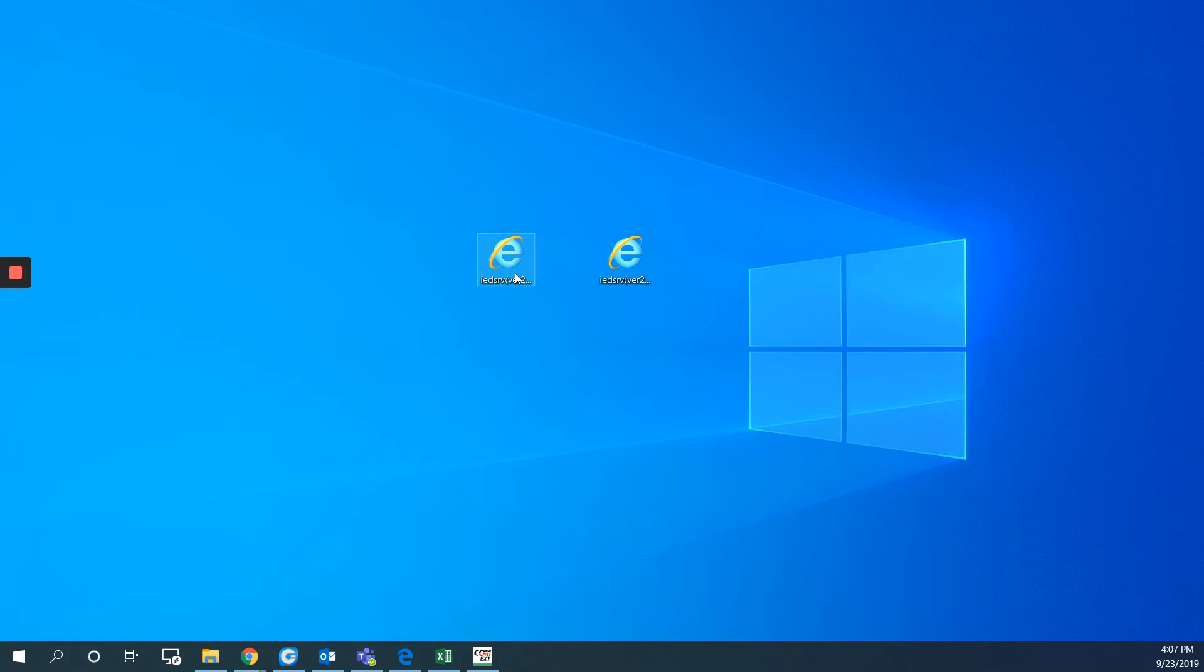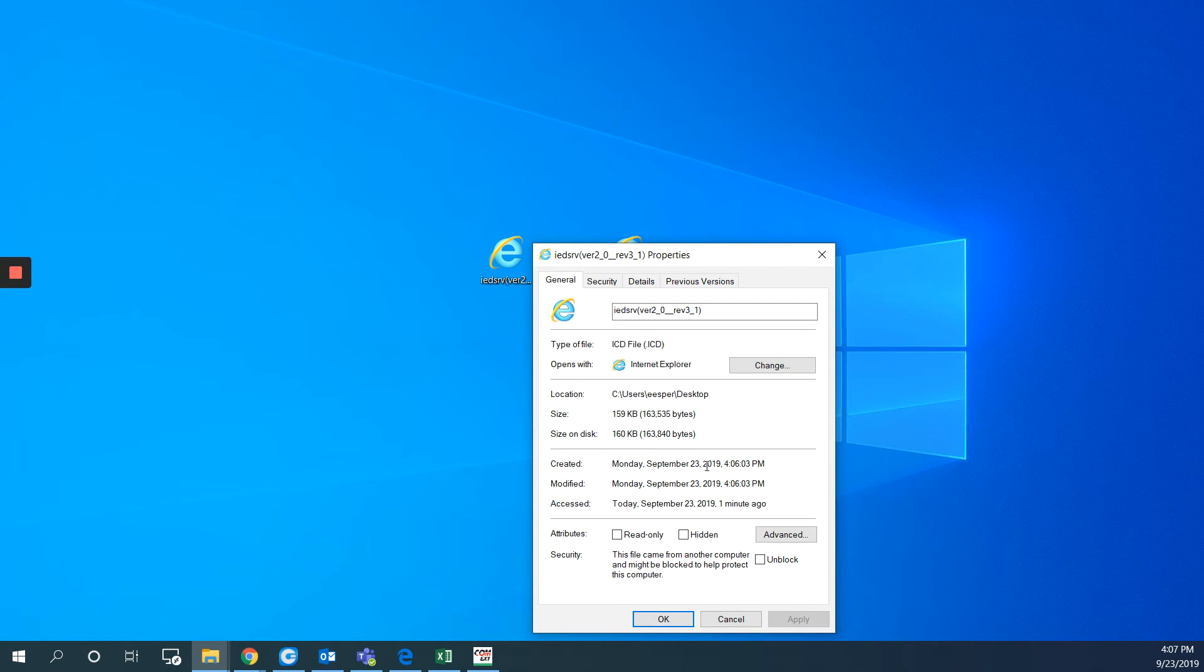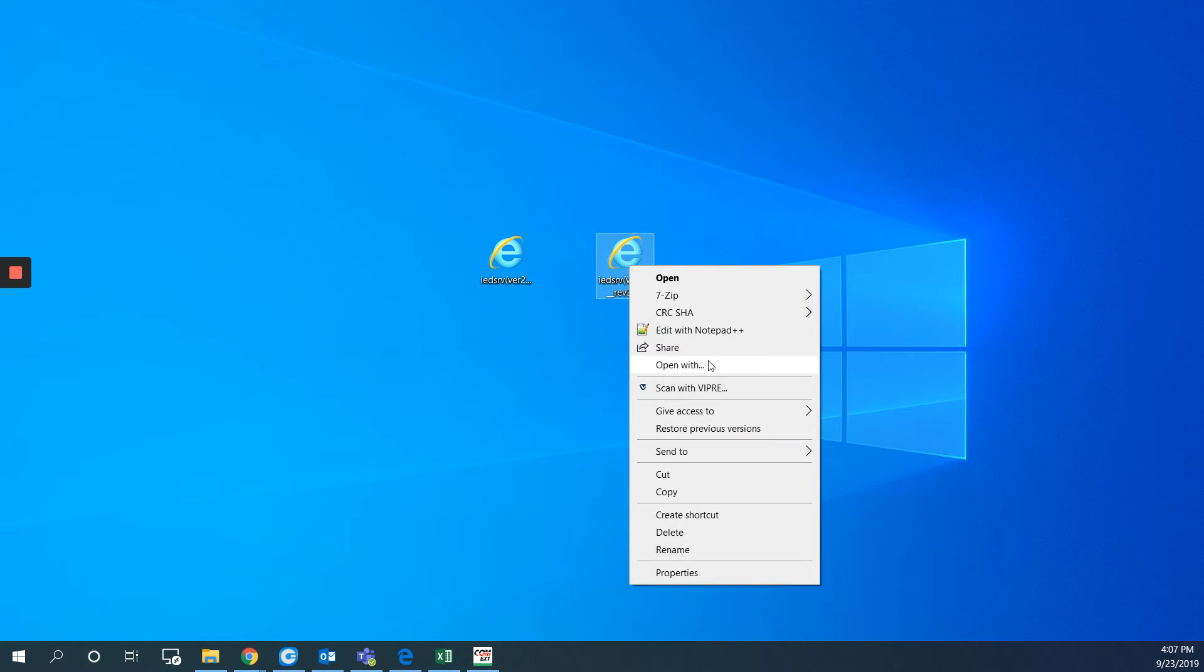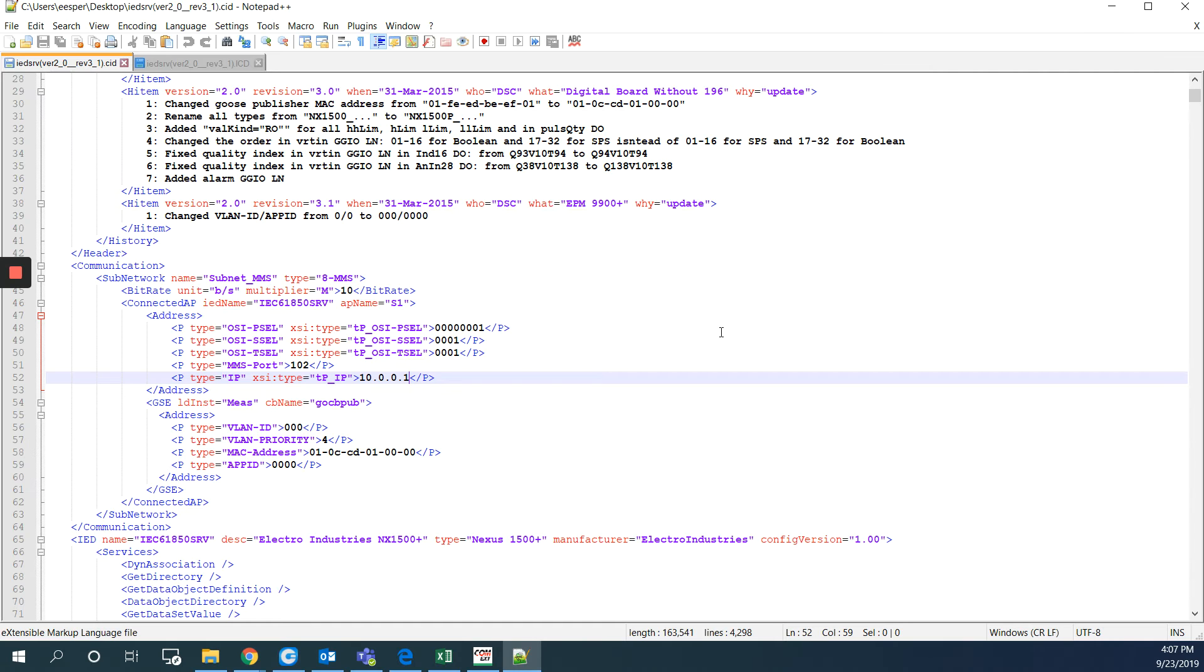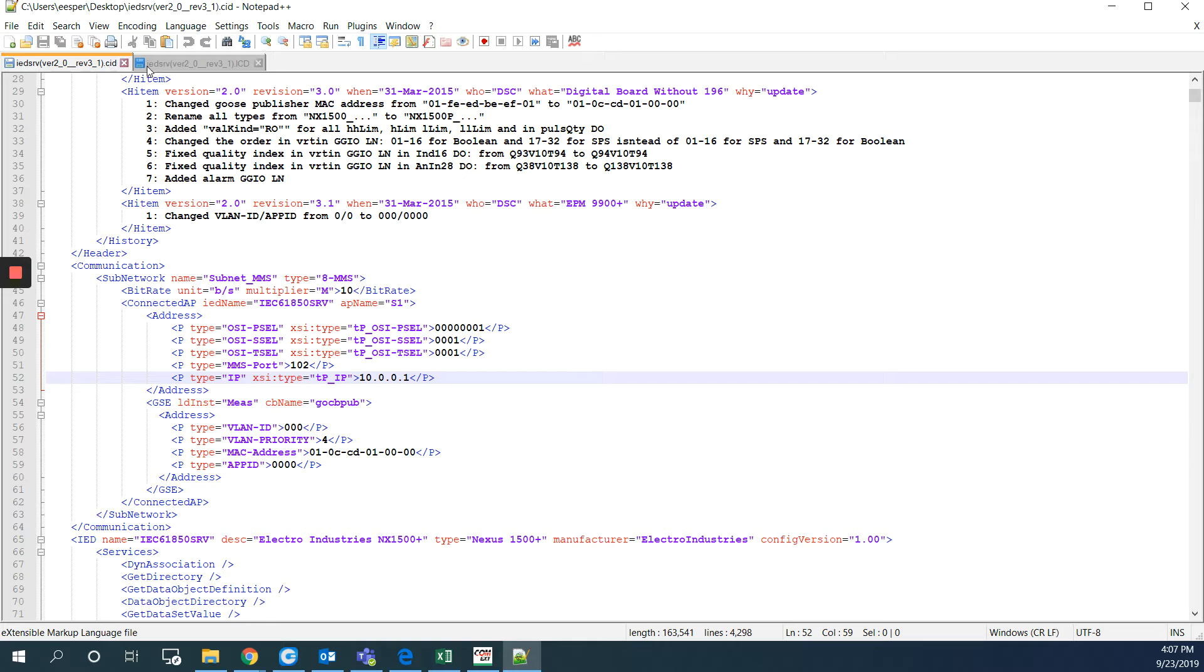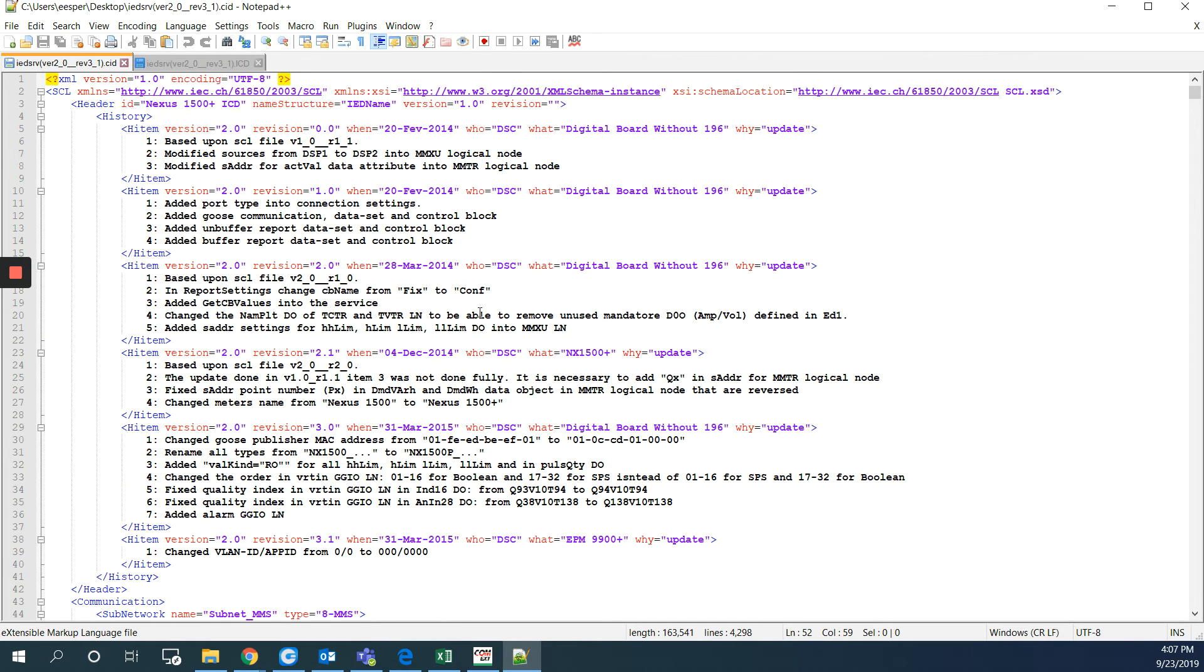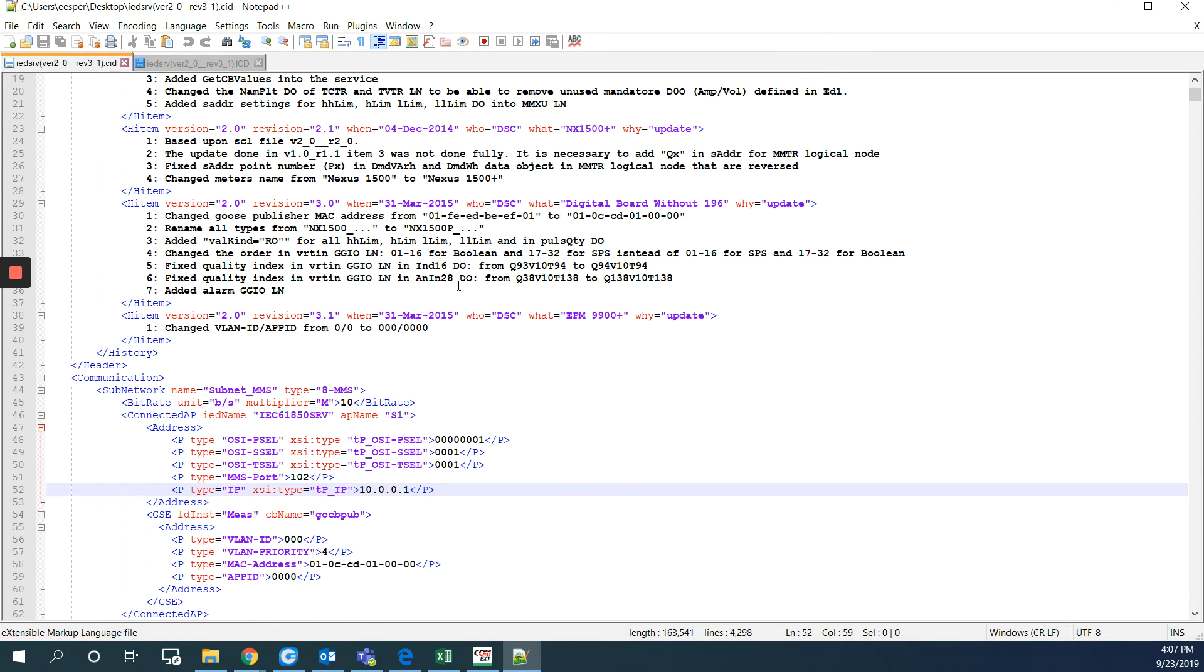I will right click on the CID file. I just want to make sure that this is the ICD so I will choose the other one. And hit edit with notepad plus plus. So make sure you have this software. On this one here I will go to the IP address. So it will start with the XML version. You can scroll down and find the IP.